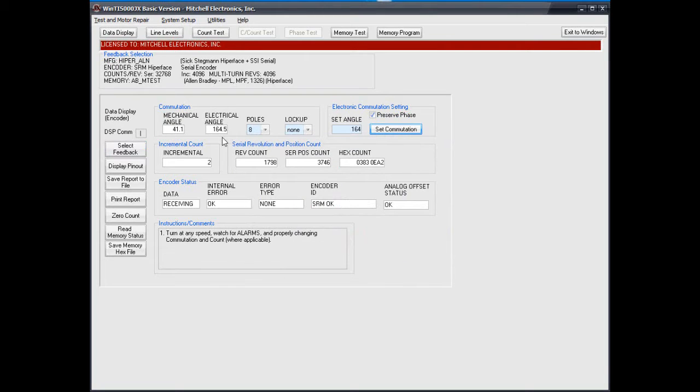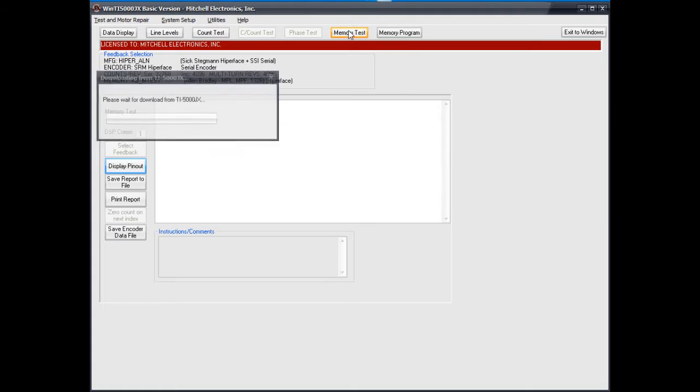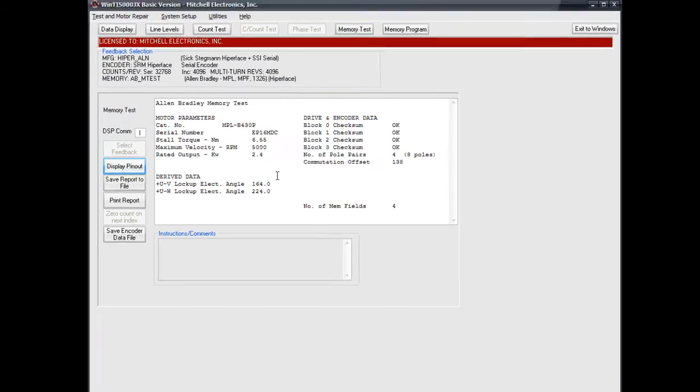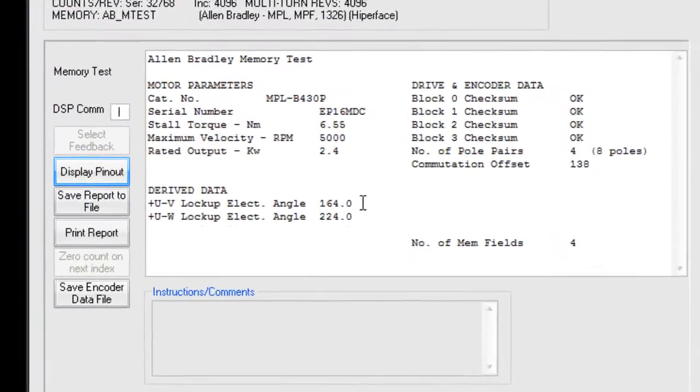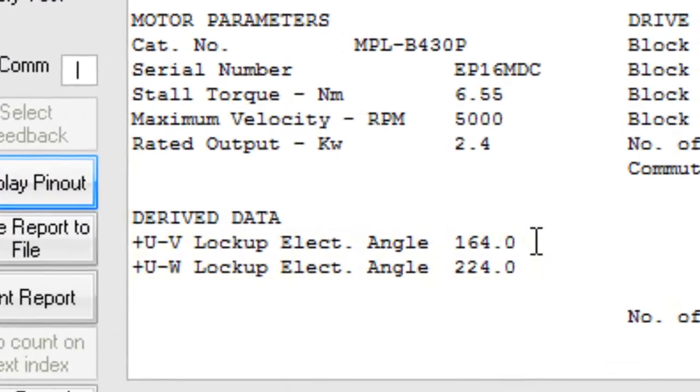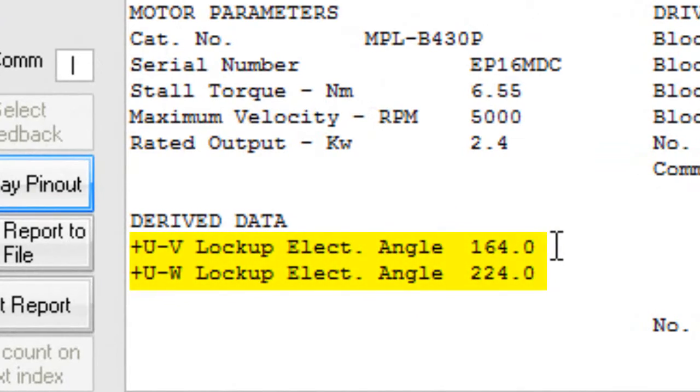Some motor brands use a standard alignment and others store a unique alignment in the encoder's memory. Make sure to check out the corresponding memory test if your motor manufacturer stores data. You will need to align the encoder to the angles listed in that memory report.